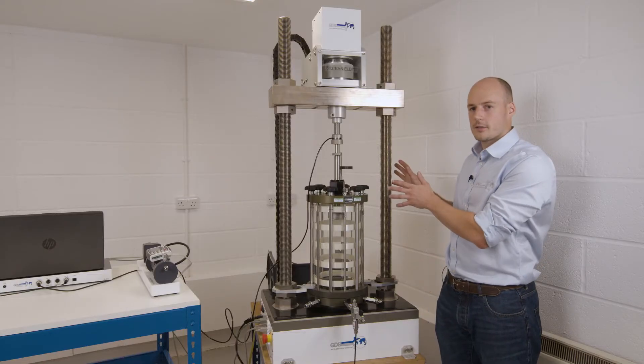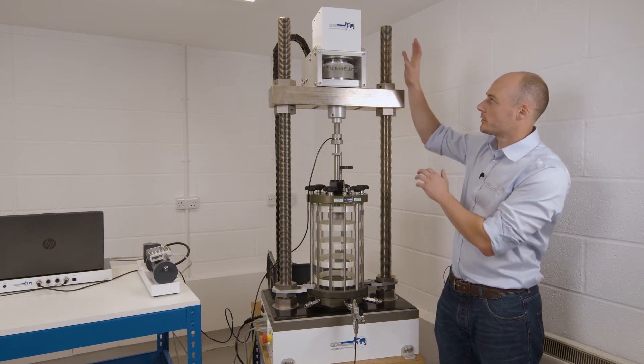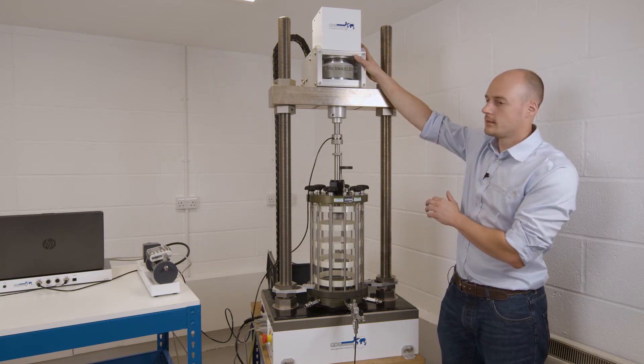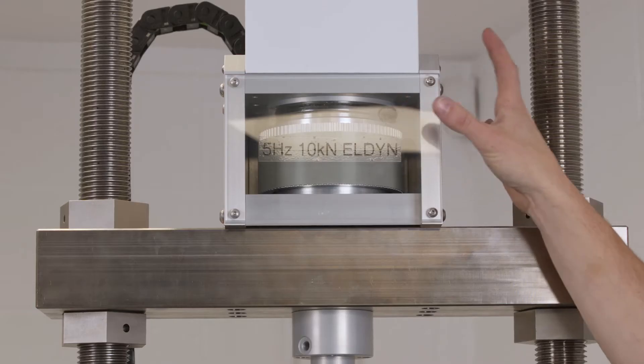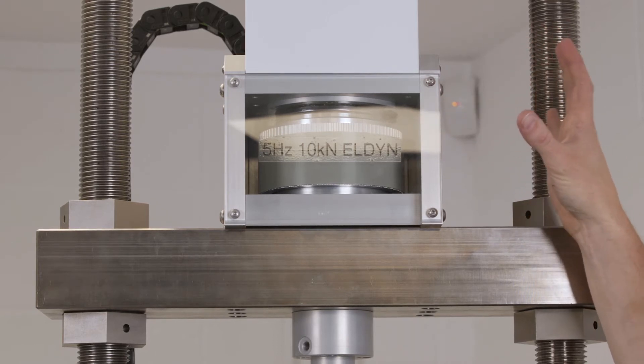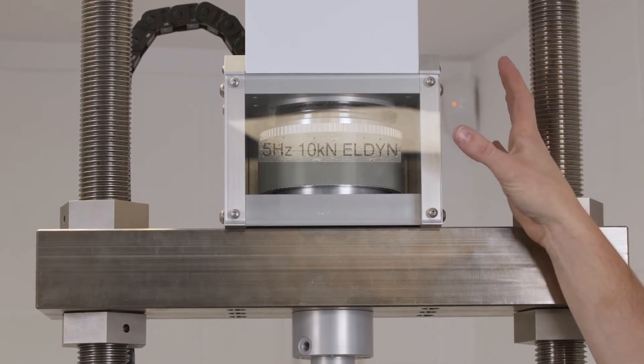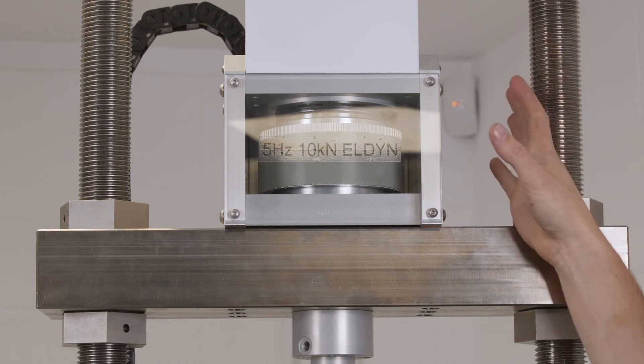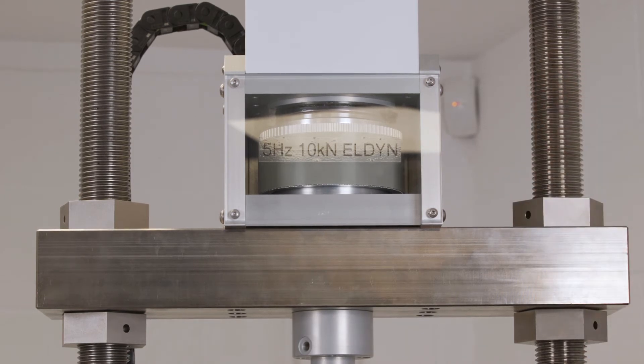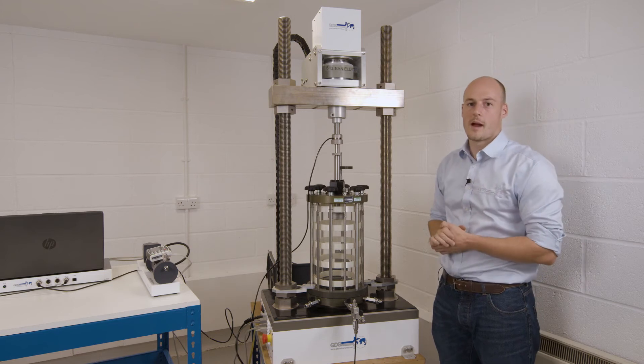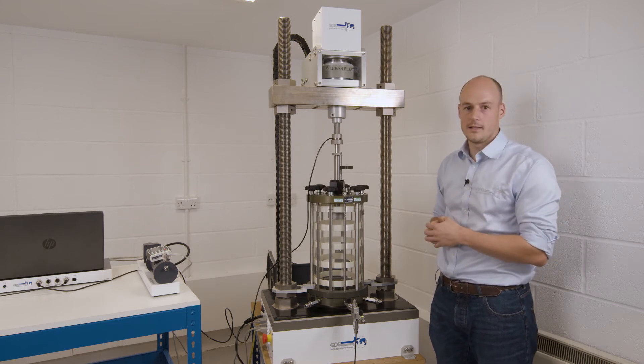Our main enterprise-level frame consists of an electromechanical actuator. This reduces any noise that you'd get from older systems using hydraulics or pneumatic pressure, no pressure in pipe work, it's a lot safer and it only uses the power requirements as and when it needs it.